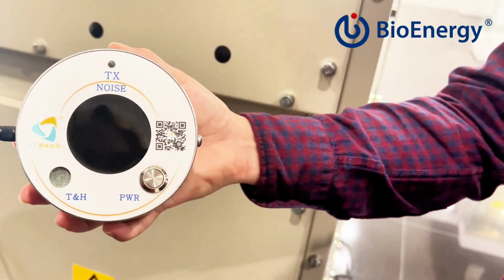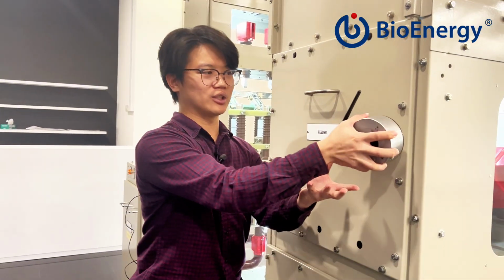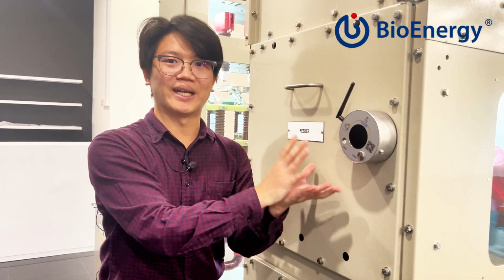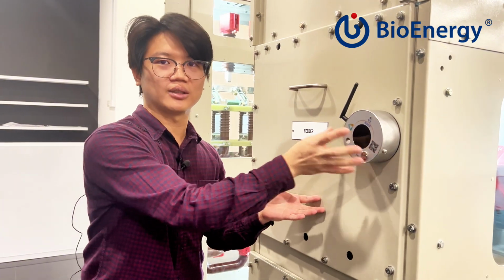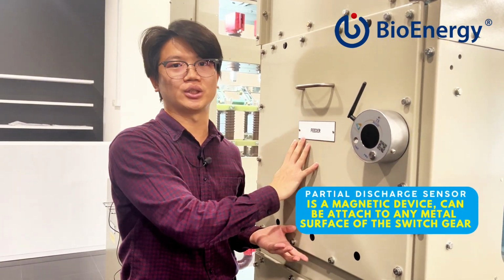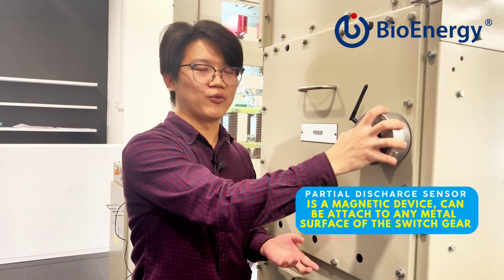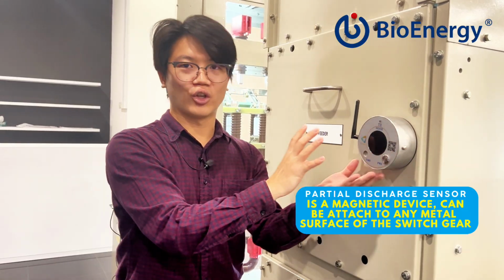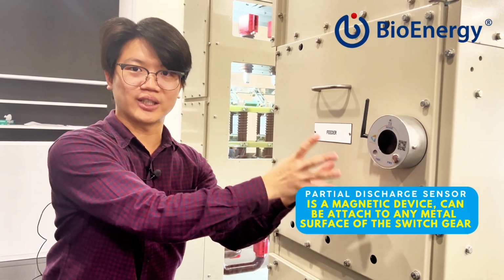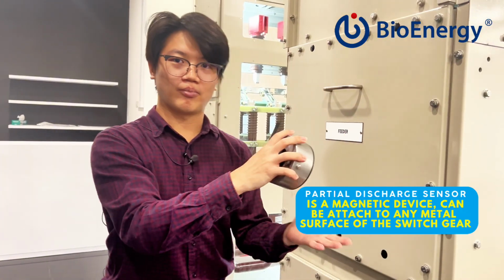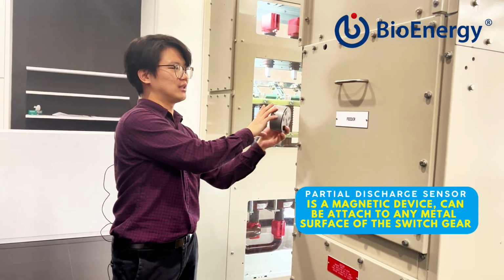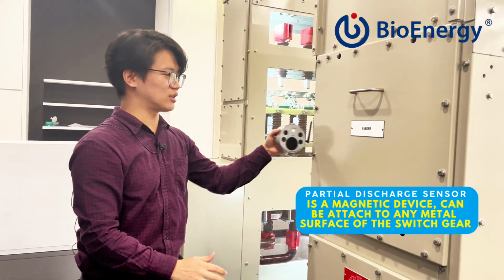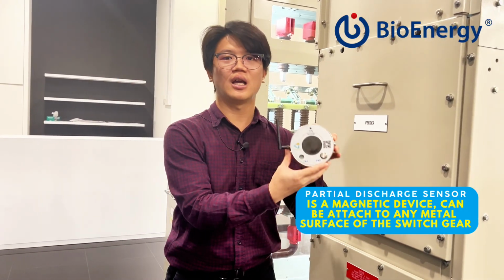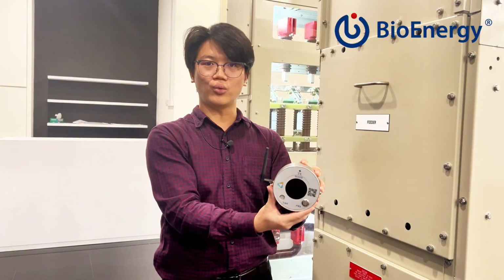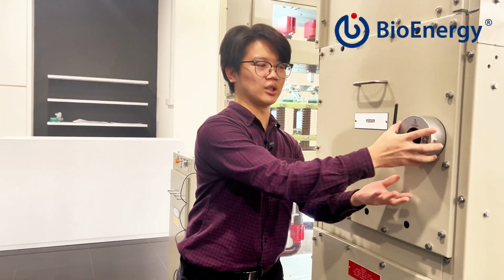You can deploy it on any of the switchgear easily. You can just snap it on. It is magnetically attached and it will monitor the partial discharge for this particular switchgear. If you feel that it is not suitable to be put on the front, you can actually magnetically stick it at the inside of the switchgear. So this partial discharge sensor will actually monitor whether there is partial discharge or not in the particular switchgears.